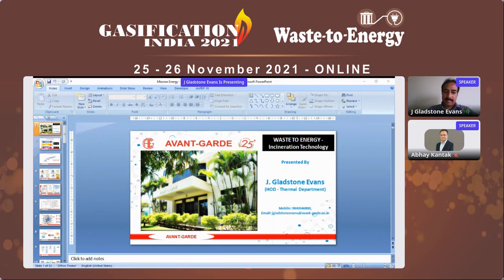In this waste to energy system, you have mainly three sections. One is the waste delivery section, then the incineration section, and the gas cleaning section. In the waste delivery section, the vehicle comes and discharges the waste in the pit. The pit is normally designed for 5 to 10 days of storage, and the waste is frequently mixed using a grab inside the pit and conveyed into the boiler. That forms the waste delivery section.